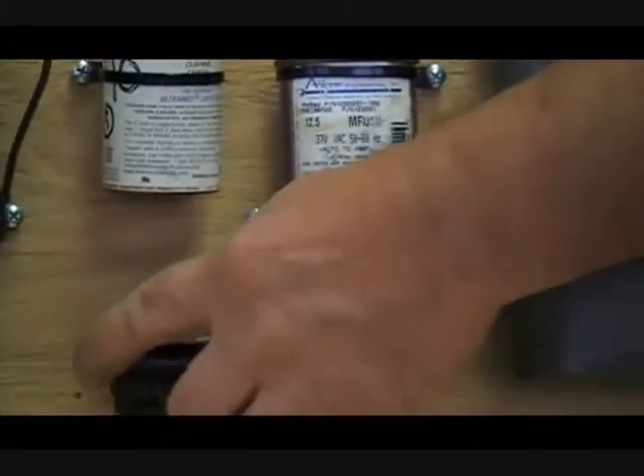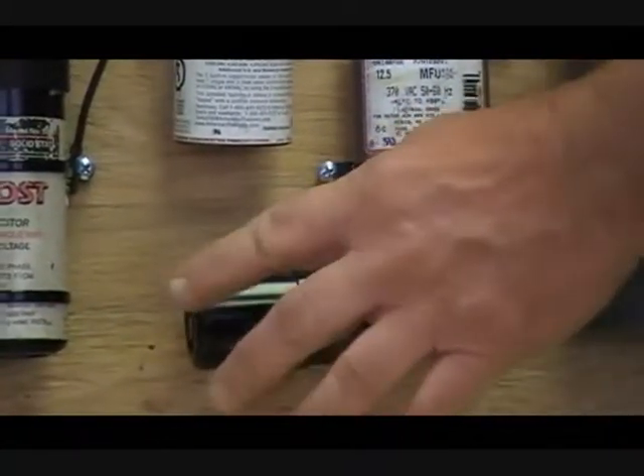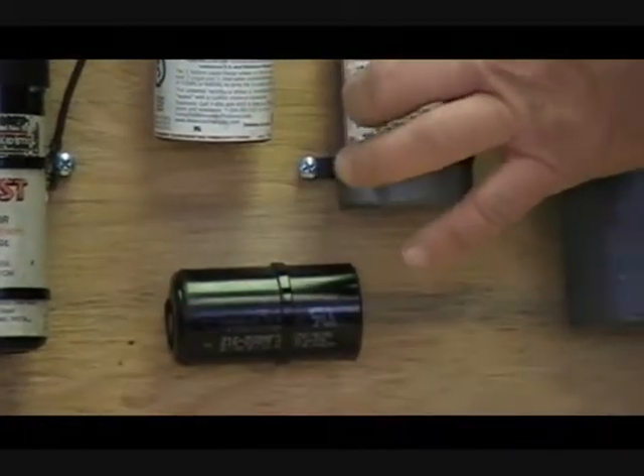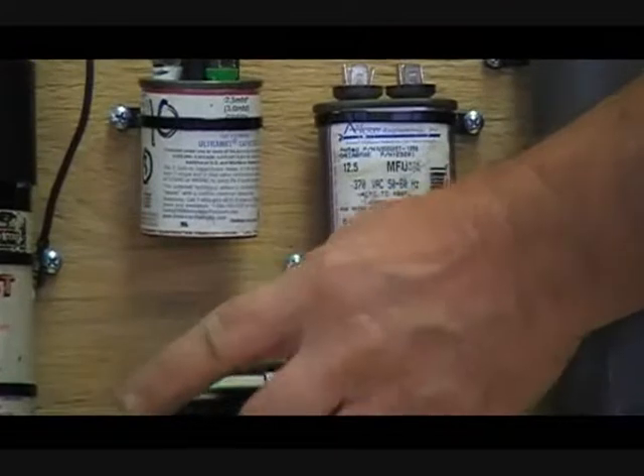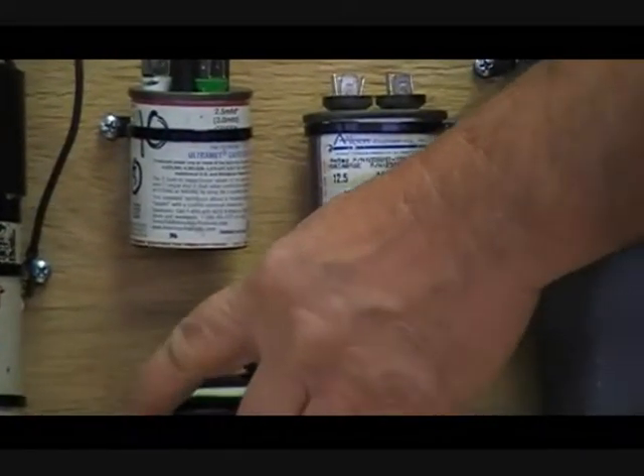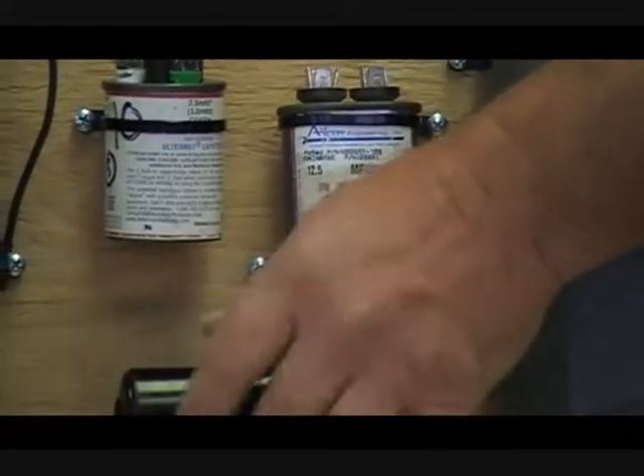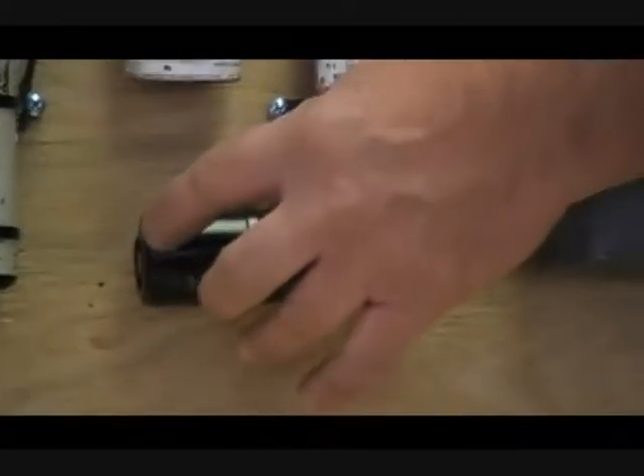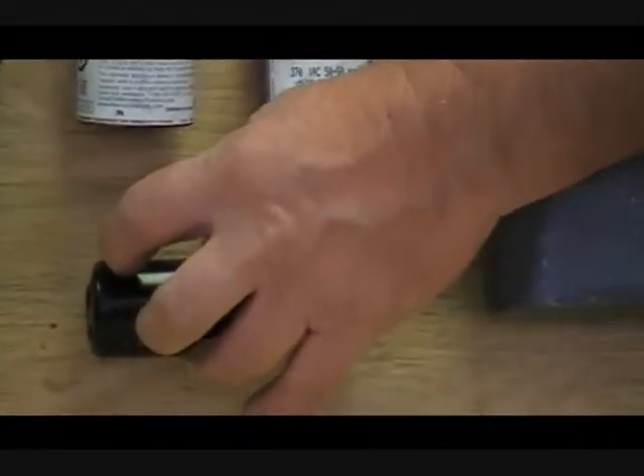Inside, there is paste inside of this particular capacitor. It's a start capacitor. Microfarads in relation to the run capacitor are going to be higher in the start capacitor. This stays in the circuit for a very short time. Within seconds, it needs to come out of the circuit, electrically disconnected. The reason being is the heat that's produced in here, a lot of heat in a short time.